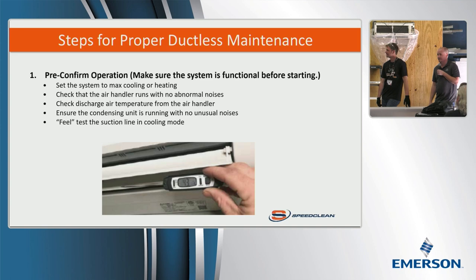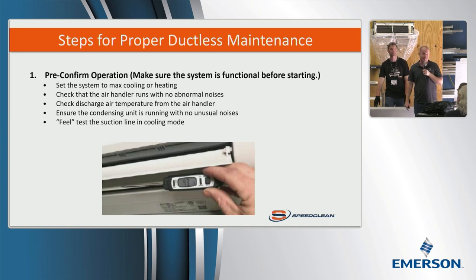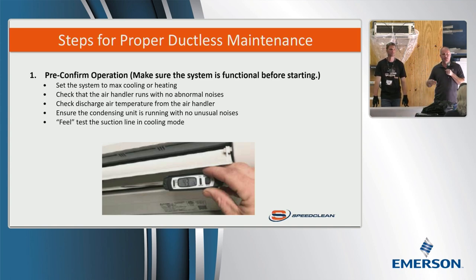But anyway, you can check your discharge air temperature. One nice thing with ductless systems is the discharge air temperature stays pretty consistent regardless. When it's working and it's at high, that's the first thing you got to do: put it in cool mode, drive the temperature way down so it goes to full capacity, and you're going to get pretty consistently the same discharge air temperature, generally 45 to 50 degrees in that range. So even when it's warmer than that, you get higher delta Ts on ductless.